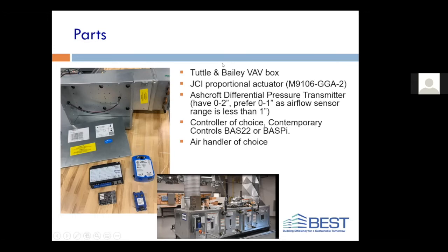So here's a couple of the items we've had: Tuttle and Bailey, the JCI actuators, Ashcroft. One thing, when you do get your differential pressure, take a look at your VAV box first to see the limits of the airflow. The limit of the airflow is probably 300 CFM, and that doesn't quite make it to 1 inch of static. It would have been nicer to have a 0 to 1 instead of a 0 to 2, because that would have given more range of the 4 to 20 milliamps.